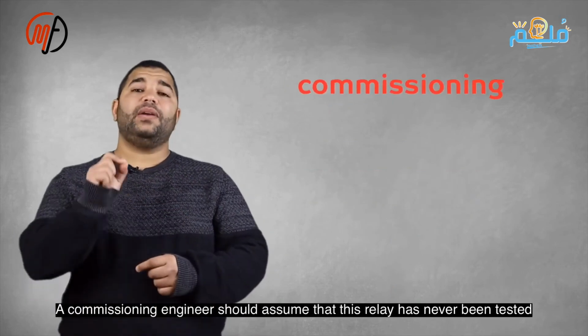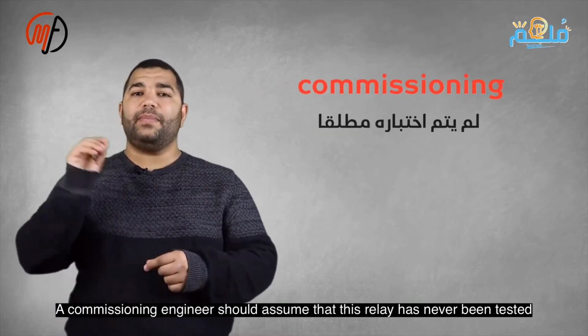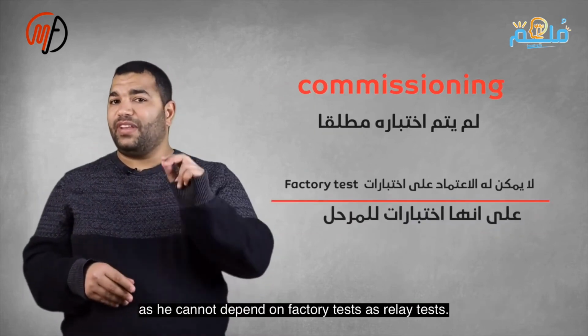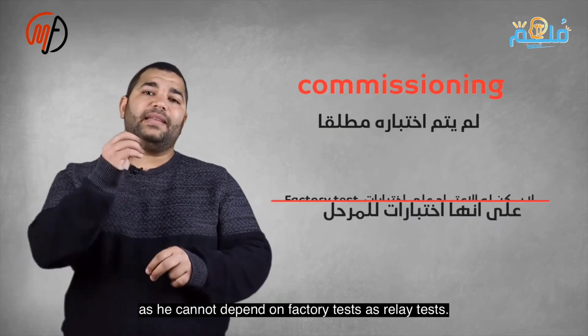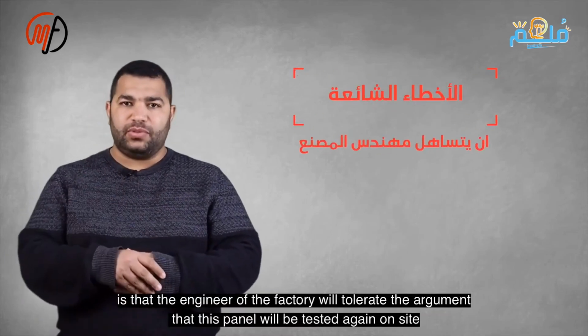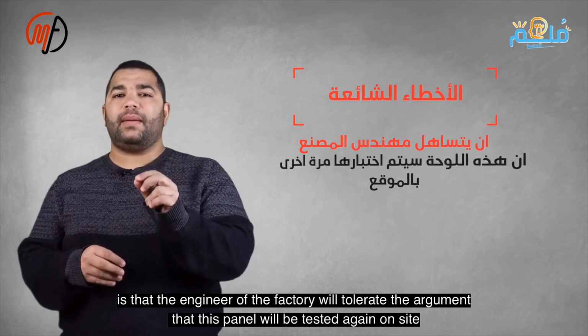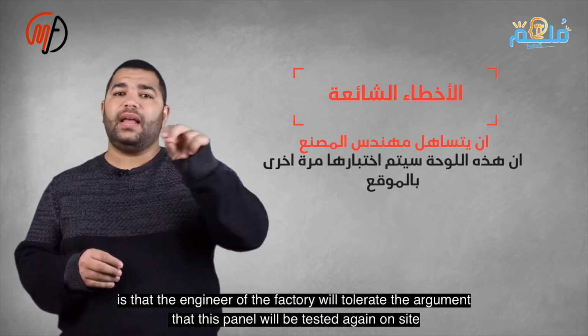The commissioning engineer must assume that this relay has not been tested before, as they cannot rely on factory tests as valid tests for the relay. One of the most common mistakes is for the factory engineer to be lenient in testing this panel, claiming that it will be retested again on site.